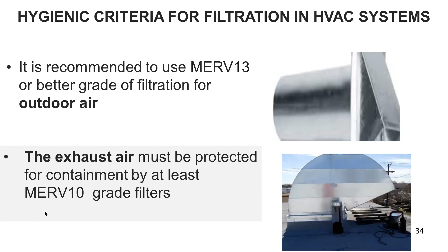Then we talk of hygienic criteria for the outdoor air and for the exhaust air. It is recommended to use MERV 13 or better grade of filtration for the outdoor air, because that is where a lot of things can come. Pollen can come. Staphylococcus aureus is one of the main things that comes with pollen in the air. Then we have the exhaust air. You have to protect the nearby places. The pathogens that you are generating, you don't want them to go to the neighborhood. So you put MERV 10 in the exhaust air. This is the recommendation.